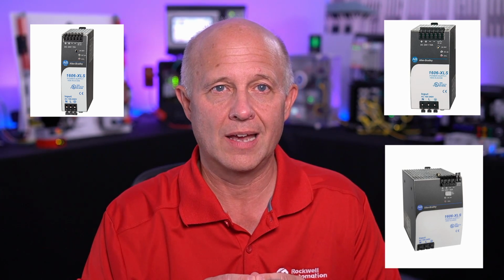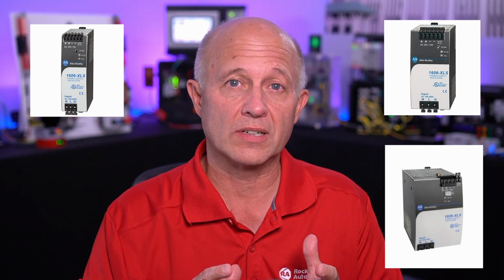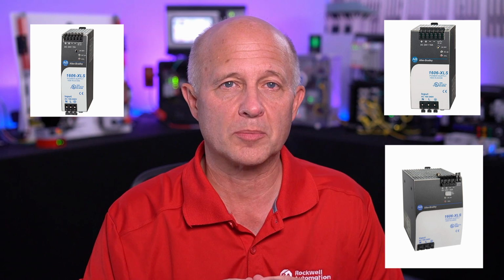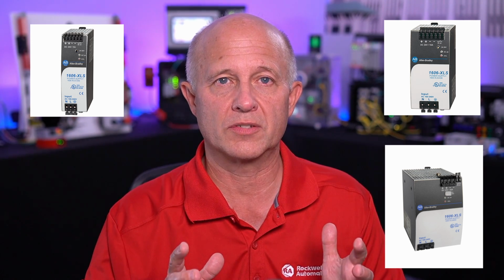This means that you're not permitted to connect any Class 2 rated field device to a 24 volt DC power circuit being fed from a power supply rated more than 4.16 amps. So for example, the commonly used 5, 10, or 20 amp power supplies are not Class 2 rated devices. Unfortunately, it's often necessary to have one of these larger power supplies in order to handle the loading for all of the low voltage devices in your system. And that's where the 1694 ECP saves the day. The 1 amp through 4 amp protection modules are offered with Class 2 ratings. This allows you to have individual Class 2 circuit protection for any of the field devices that require it, while still being able to size your power supply for the larger combined loads.